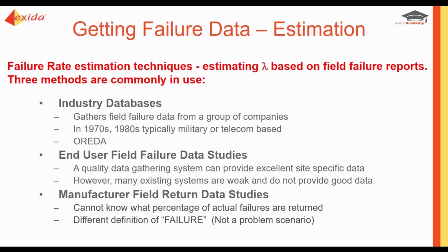This was first started in the 70s or 80s in military databases. There are telecom databases from these techniques. More recent is OREDA, the offshore reliability data, an organization that analyzes a lot of the offshore and subsea platforms in the North Sea. They once again take information from multiple different companies, analyze it, and a university runs their statistical analysis, and then they publish a database with that information.